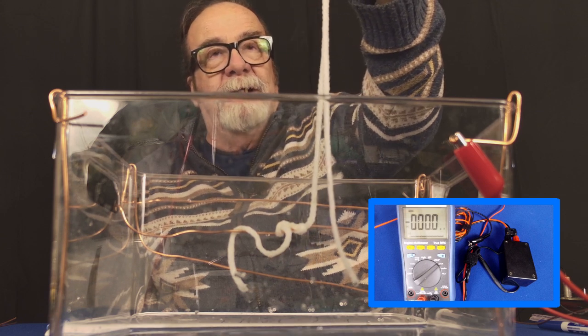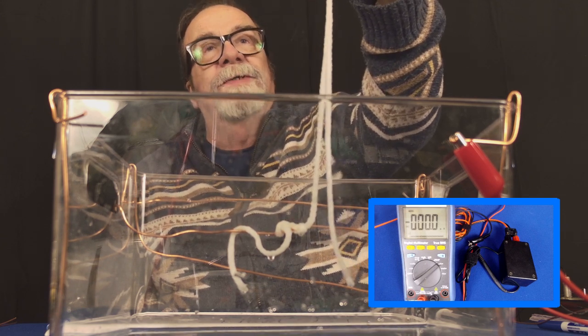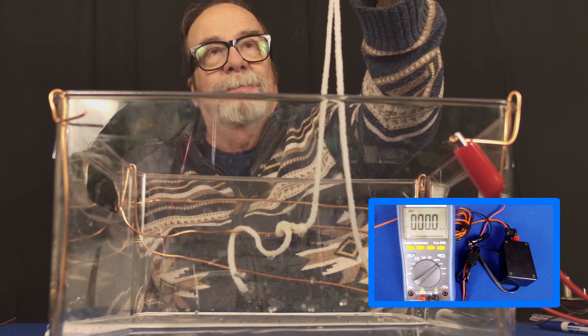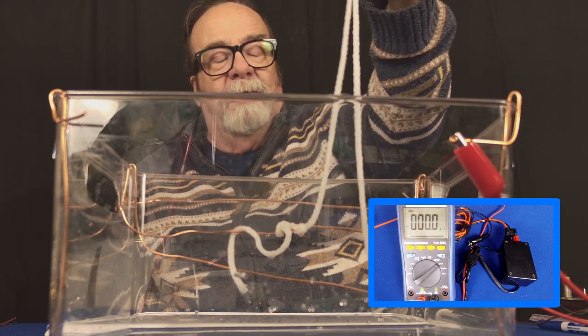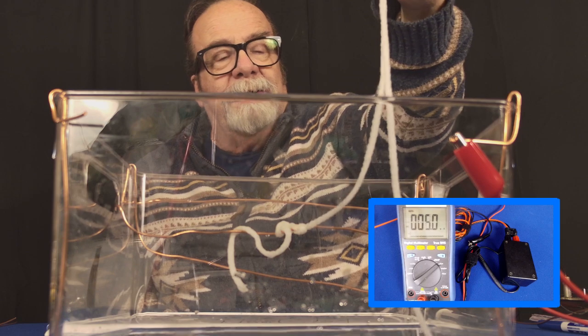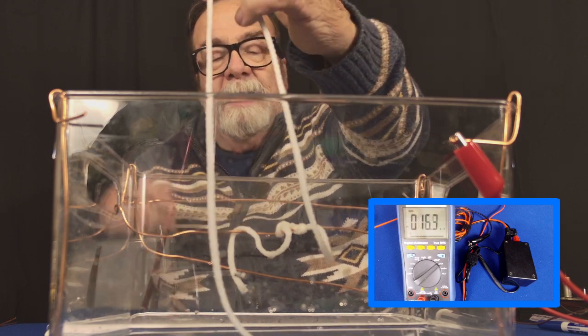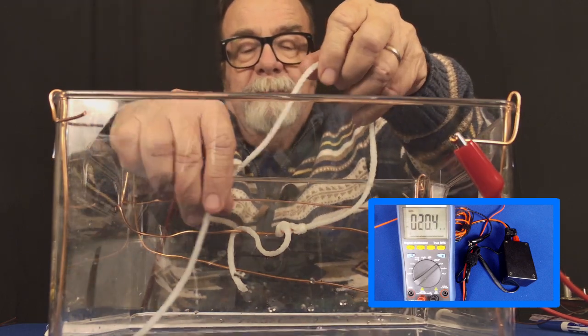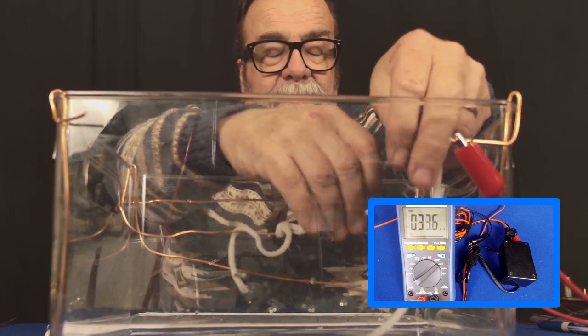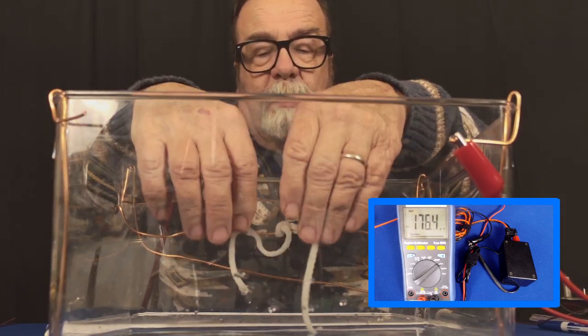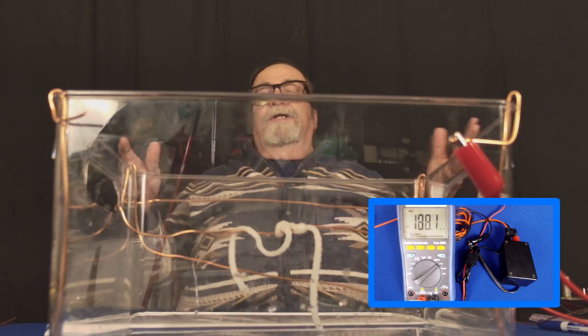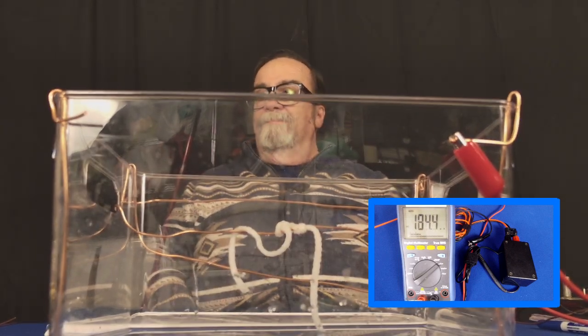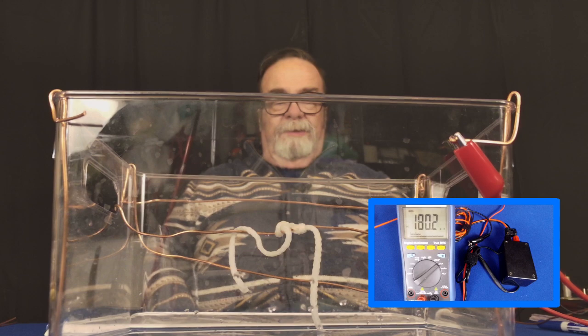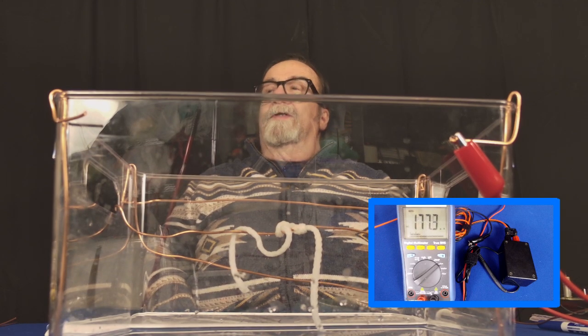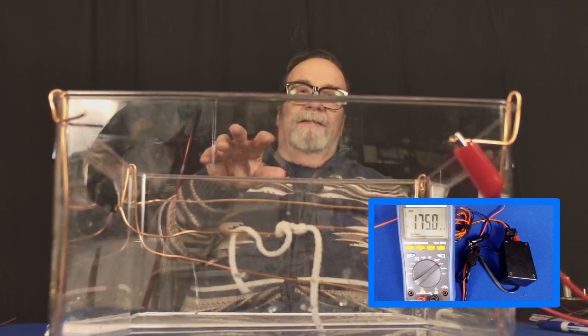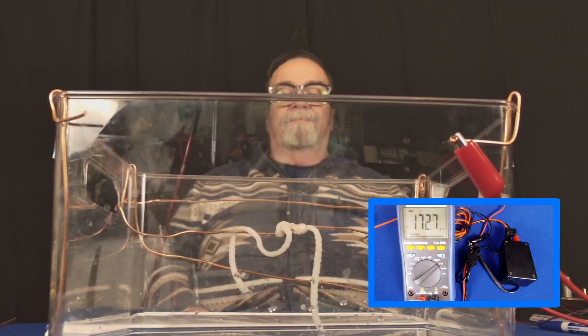Now, think of this, like I said, as a conduit full of water. And of course it fills with water when it rains, and then when it stops raining it may leak back out into the ground and somewhat dry out. So now it's going to rain again and the conduit's going to fill with water and it's going to cover this wire, and it's going to be even worse if this wire is damaged. If it's got an abraded point that's showing bare copper, it's going to be worse. So this is how you can find these grounds in wet conduits.